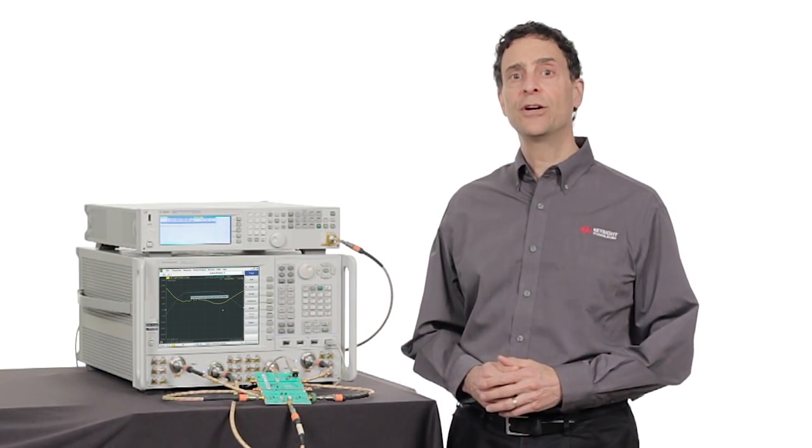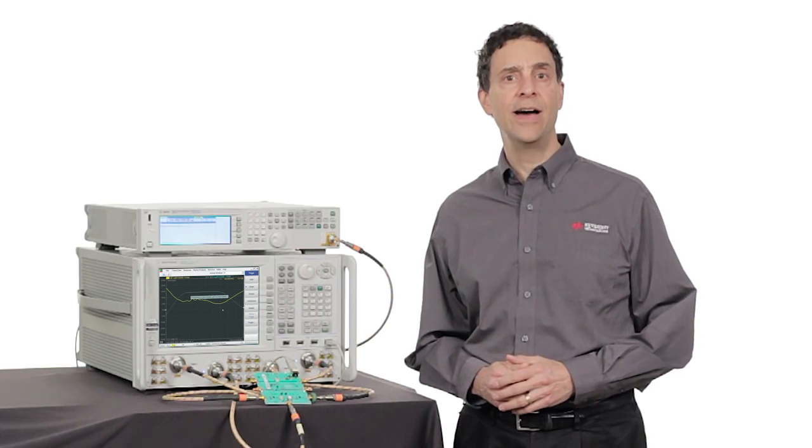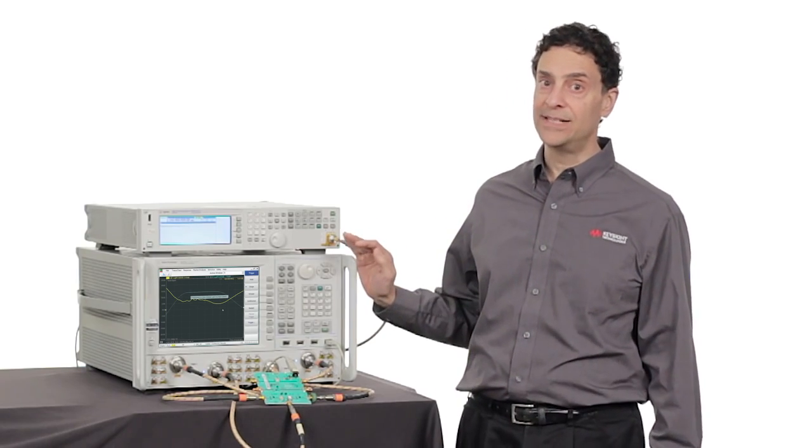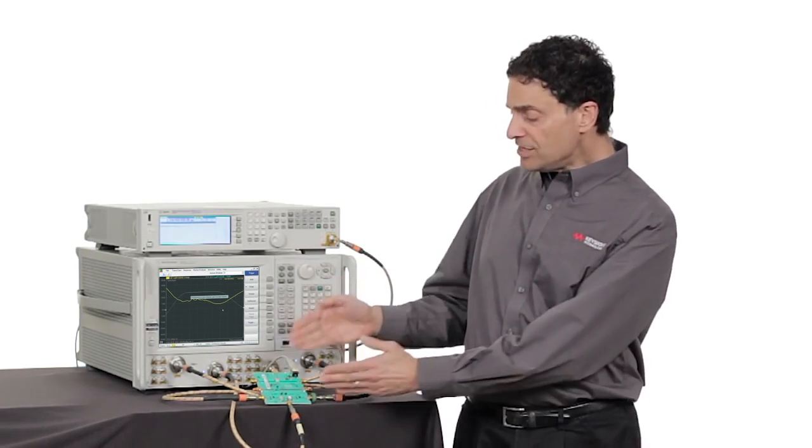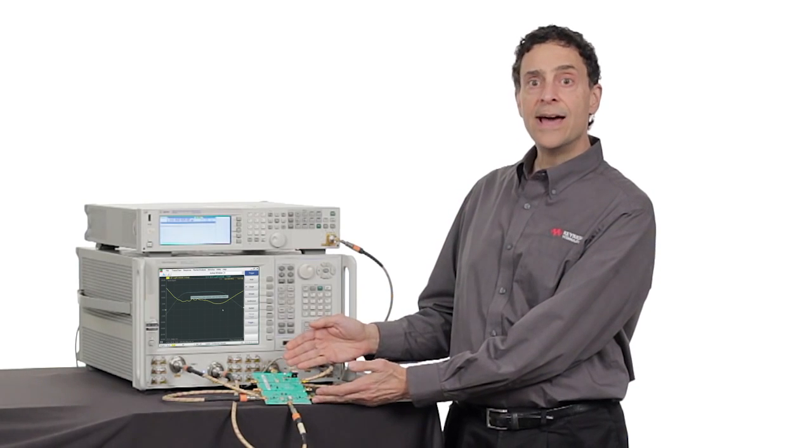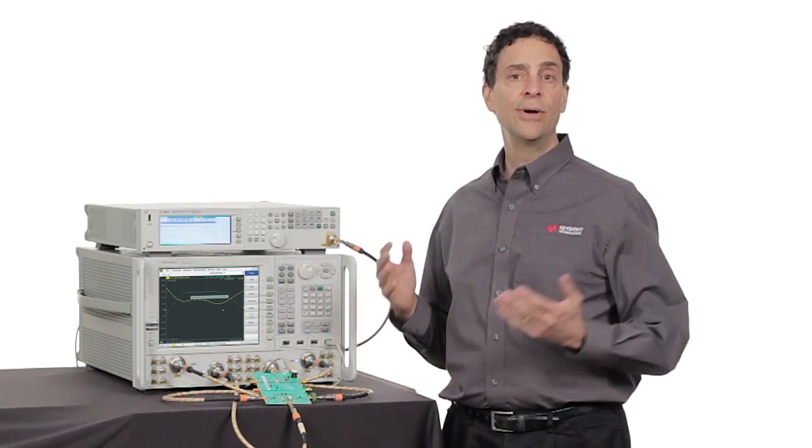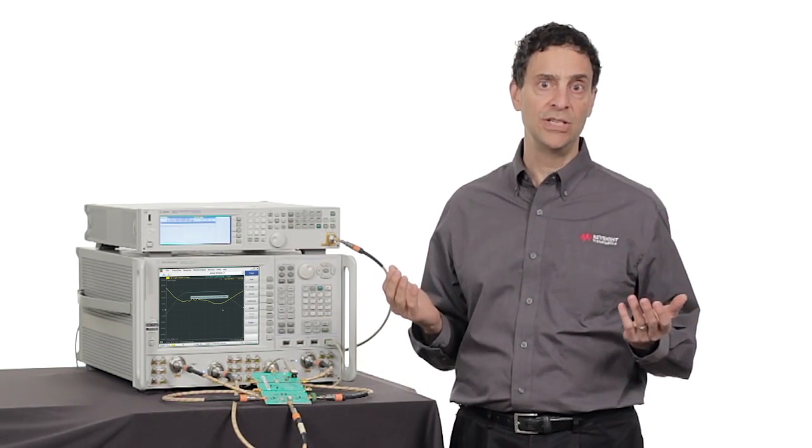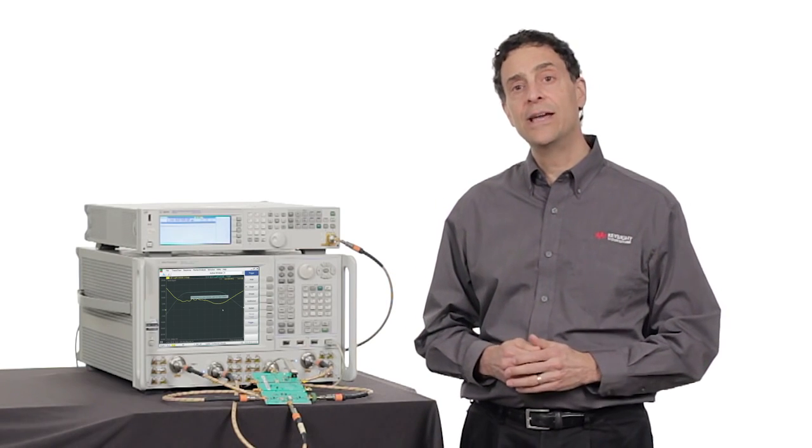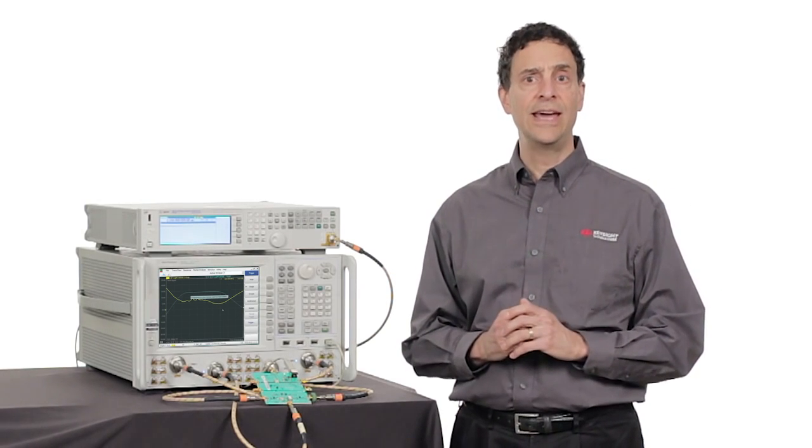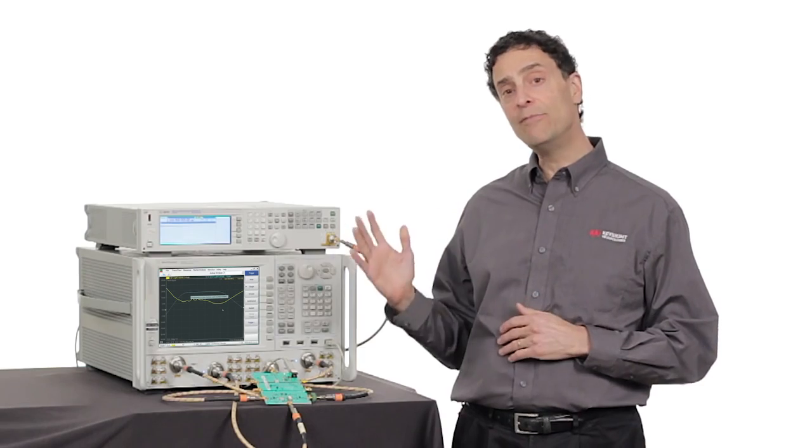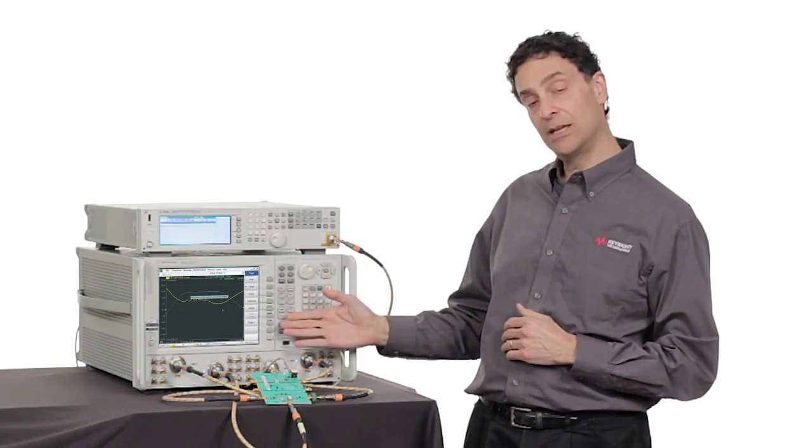This condition often occurs when measuring high-gain devices with an incorrect test setup. However, this frequency converter only has 8 dB of gain, so it can't be overdriving the noise receiver. A spectrum analyzer would be very useful in this case to determine if an out-of-band signal was causing the overload.